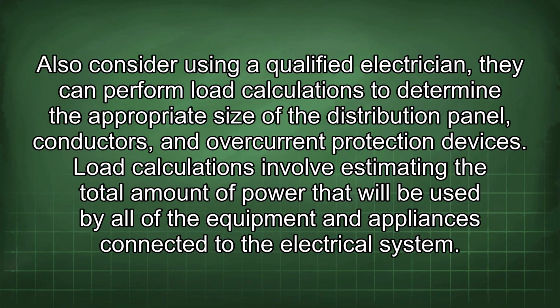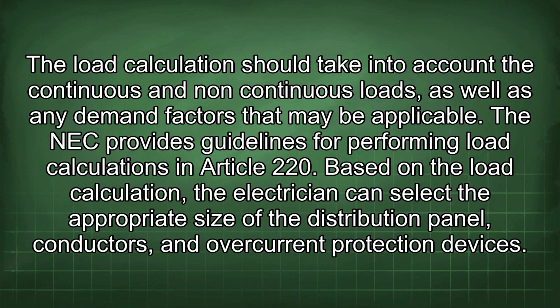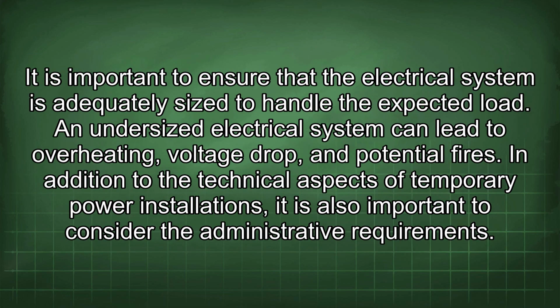Load calculations involve estimating the total amount of power that will be used by all of the equipment and appliances connected to the electrical system. The load calculation should take into account the continuous and non-continuous loads, as well as any demand factors that may be applicable. The NEC provides guidelines for performing load calculations in Article 220. Based on the load calculation, the electrician can select the appropriate size of the distribution panel, conductors, and overcurrent protection devices. It is important to ensure that the electrical system is adequately sized to handle the expected load. An undersized electrical system can lead to overheating, voltage drop, and potential fires.